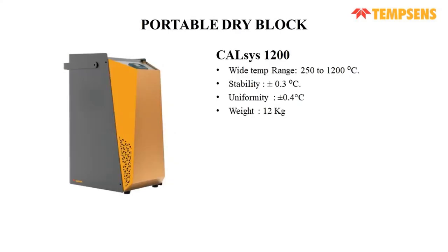Next, we have CALsys 1200. The temperature range of this model is 250 to 1200 degrees centigrade, the stability is plus minus 0.3 degrees centigrade, the uniformity is plus minus 0.4 degrees centigrade, and the weight of this model is just 12 kgs. These are for the portable models.